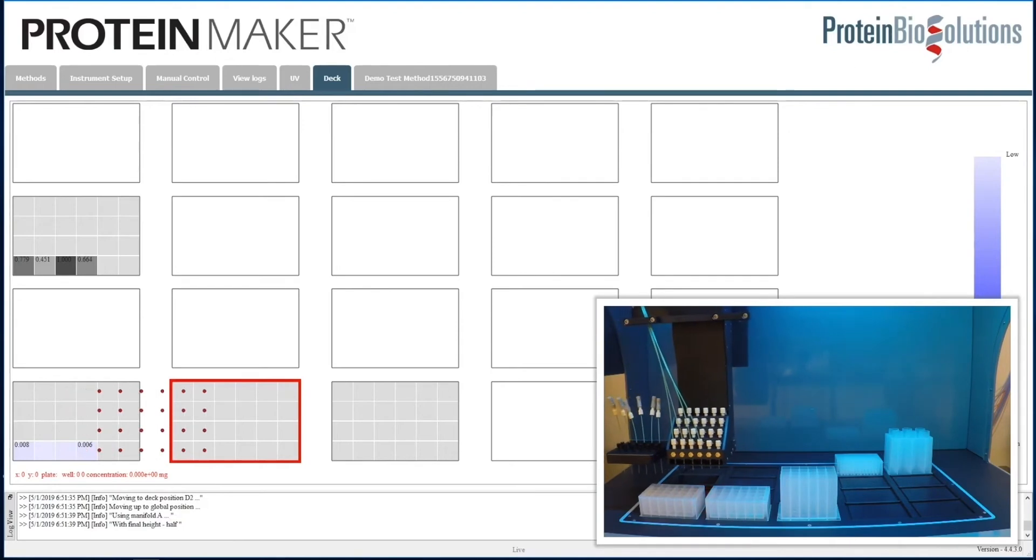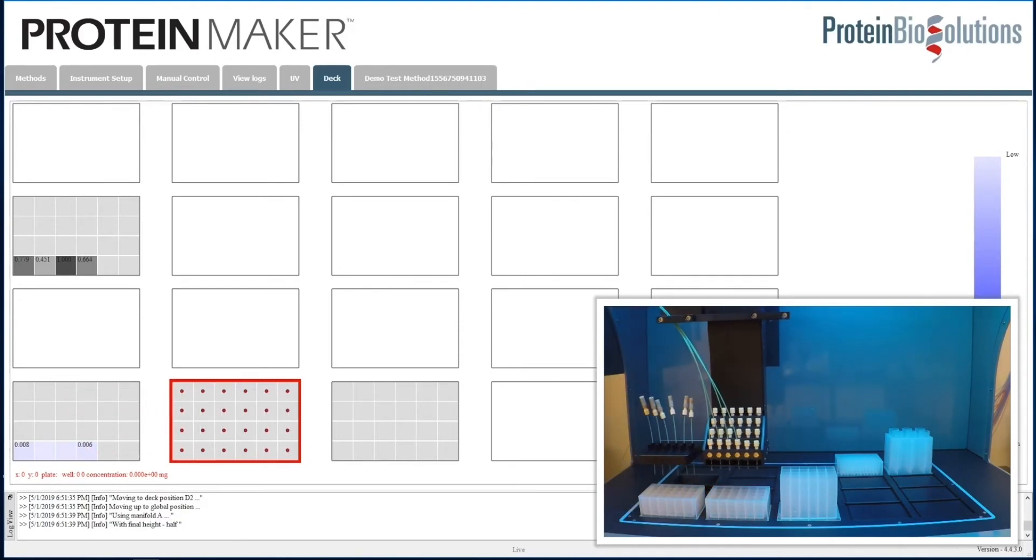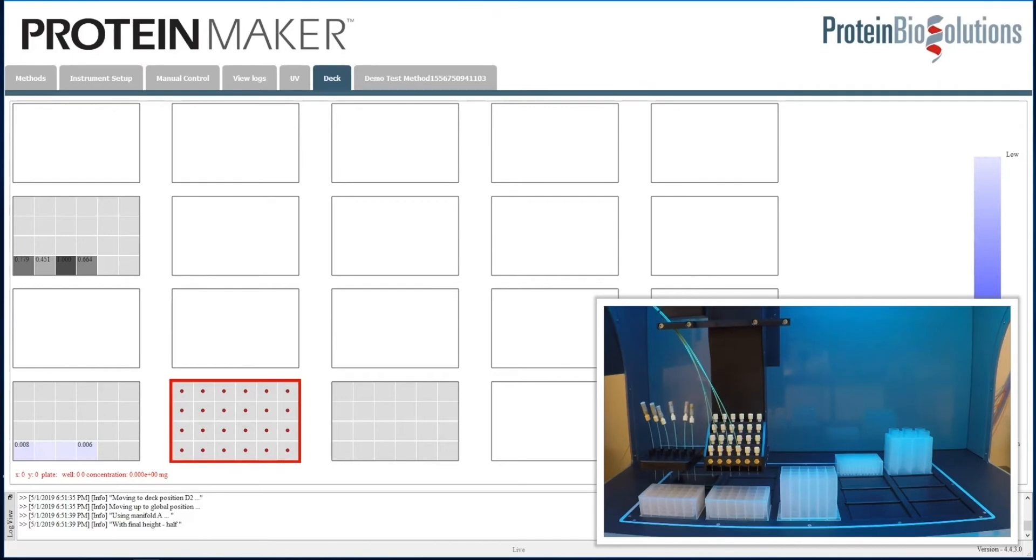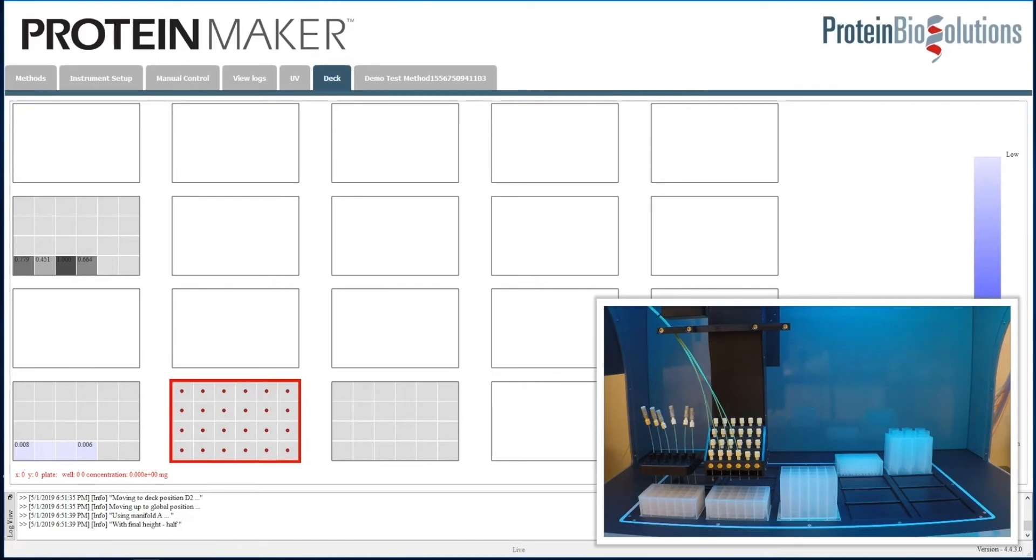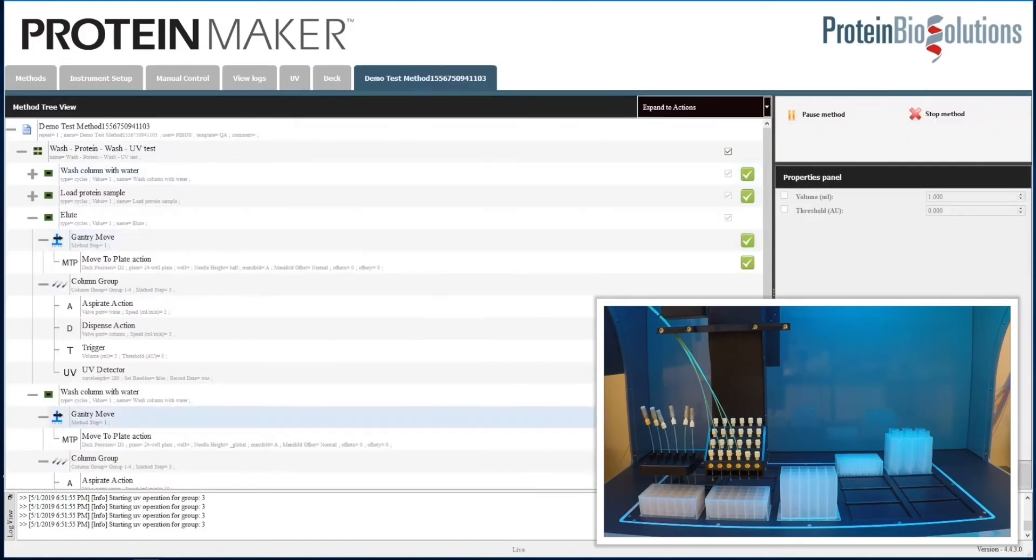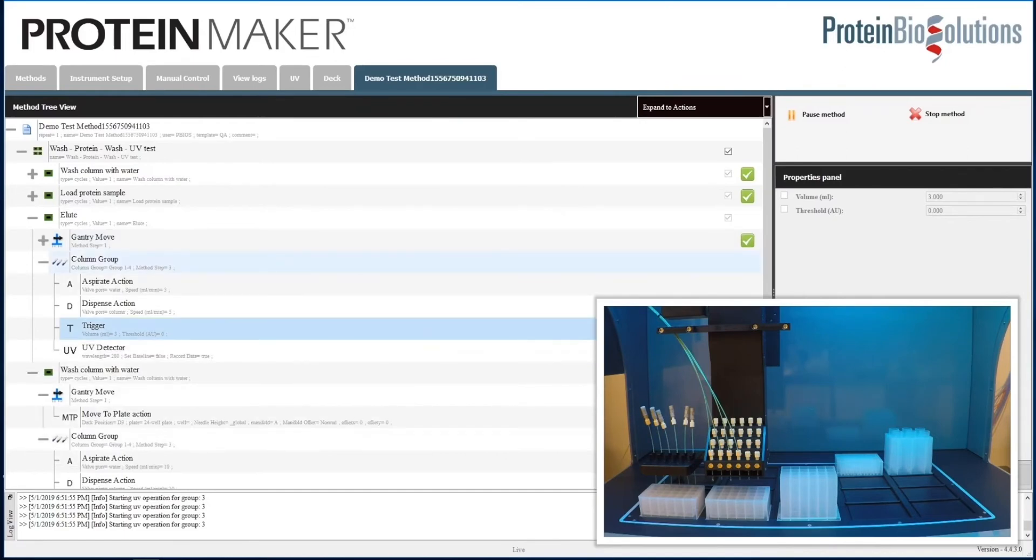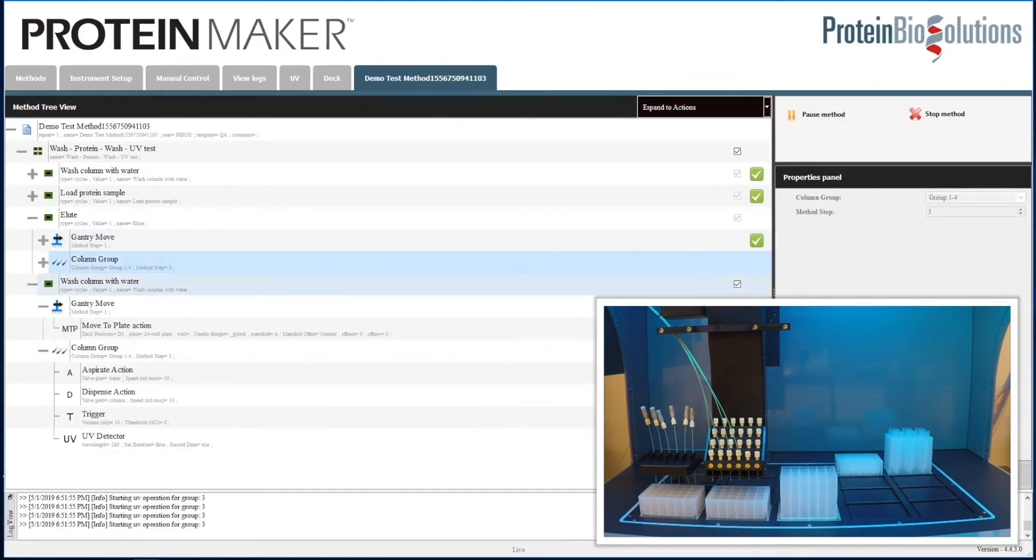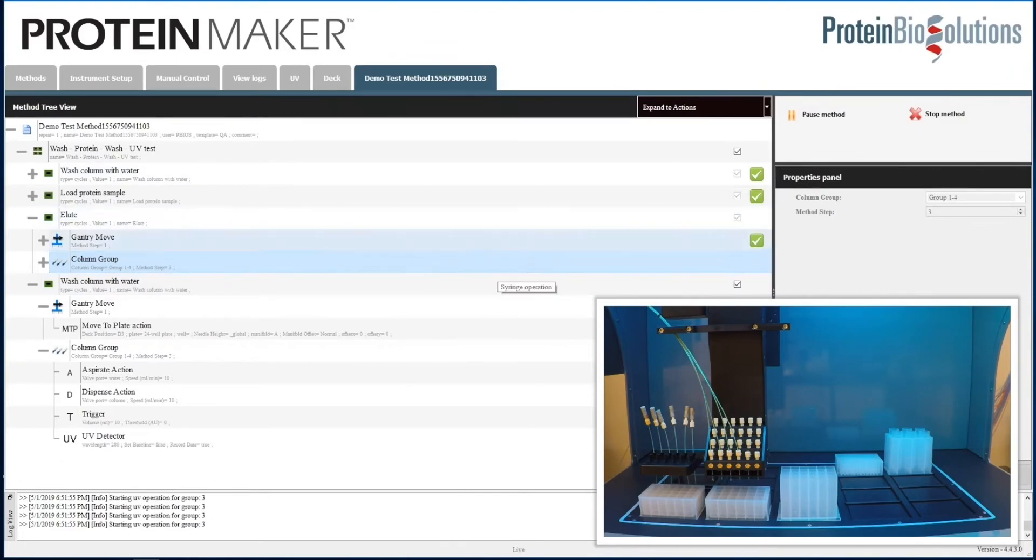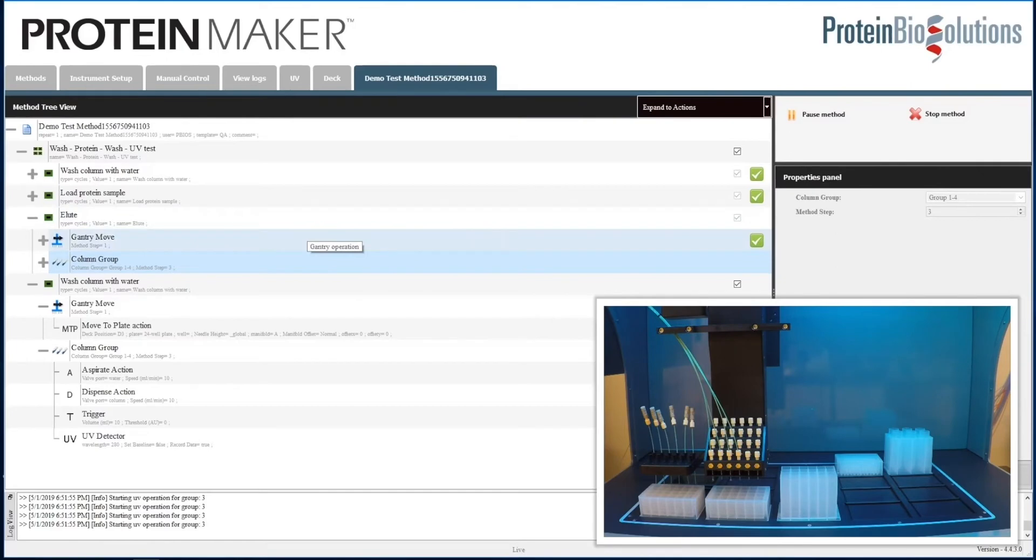Here in the deck view, you see that some of the wells in the crosshatched area are turning a light shade of blue. What's happening is that the deck view is logging the UV absorbance information. Collective absorbance information is logged for each well position. The more absorbance that is logged, the darker blue the well will become. This deck view is constantly updating so that it produces a relative picture of where the most absorbance has been logged over the whole fraction collection deck.